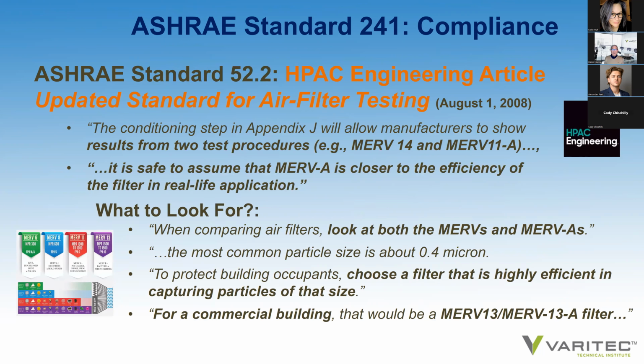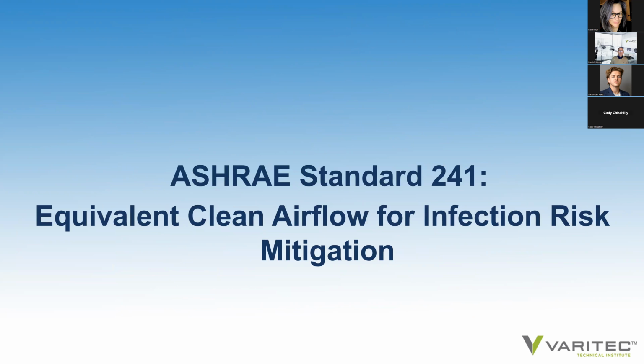The HPAC article goes on to say it is safe to assume that MERV-A is closer to the efficiency of the filter in real-life application, and it offers this advice: when comparing air filters, look for both the MERVs and the MERV-A ratings. It is also to protect building occupants, choose a filter that is highly efficient in capturing particles of the 0.4 micron size. So for a commercial building, per ASHRAE's Epidemic Task Force guidelines of meeting MERV 13, use MERV 13A rated filters if you want to make sure that that filter maintains its efficiency throughout its operating life in a building. So the objective of ASHRAE Standard 241 is to provide an equivalent clean airflow at the breathing zone for infection risk mitigation.